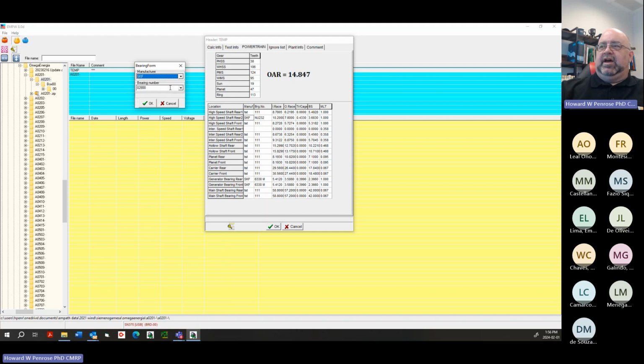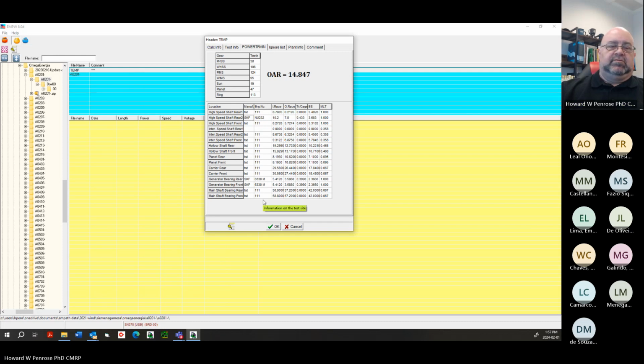You could type in, let's say, NU. As I put that in, or I can select it - it's a very large database. Then it'll find it, click on it, click OK, and it'll populate that spot. It'll put in all the multipliers - inner race, outer race, cage, and ball spin. So when it identifies a problem, I can identify the component of the bearing that's causing trouble.